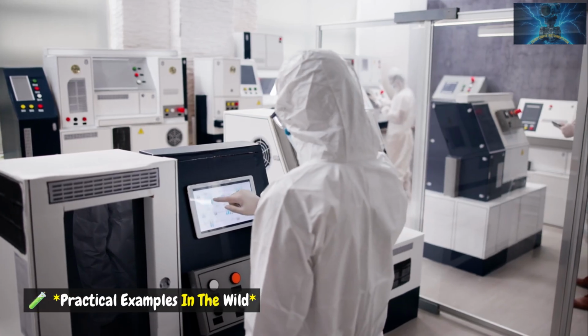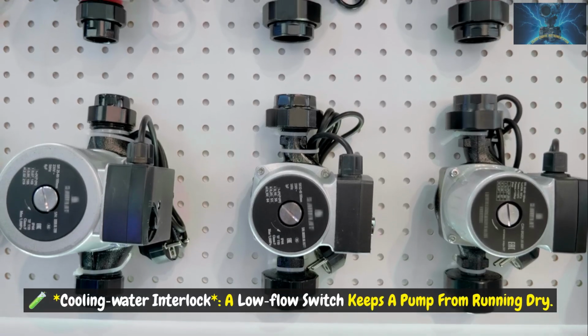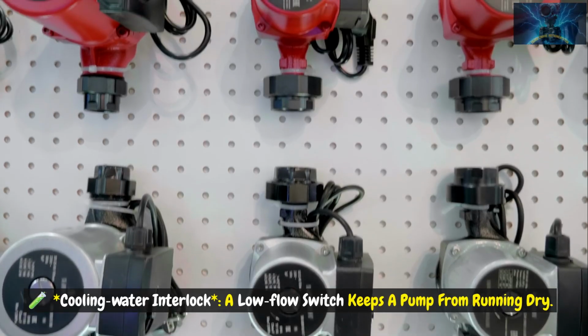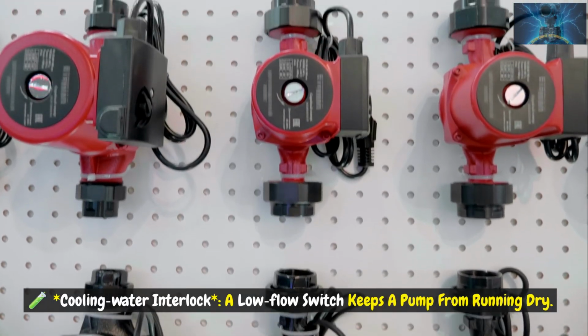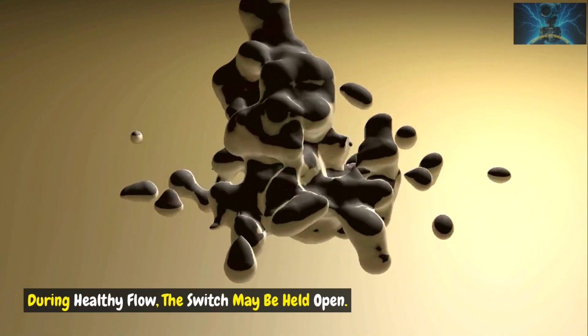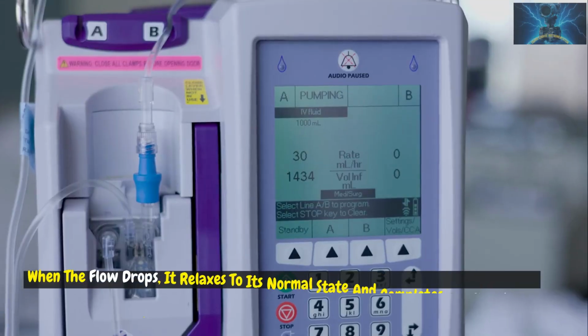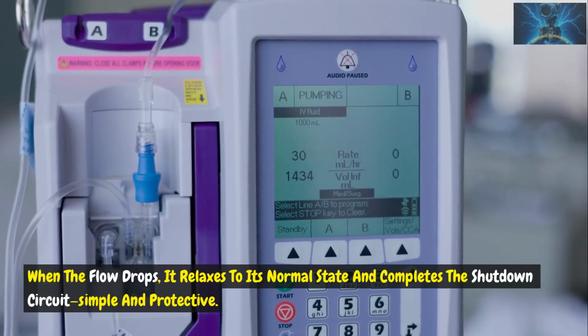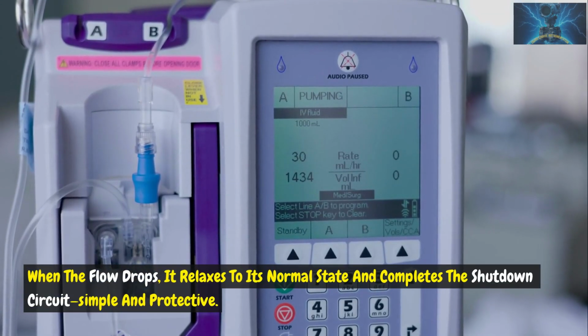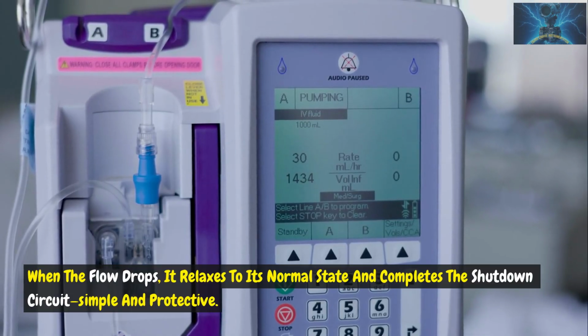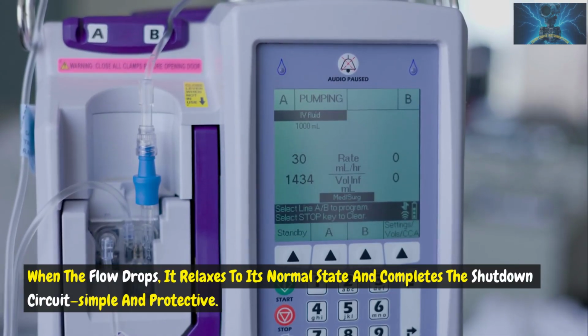Practical examples in the wild. Cooling water interlock. A low-flow switch keeps a pump from running dry. During healthy flow, the switch may be held open. When the flow drops, it relaxes to its normal state and completes the shutdown circuit, simple and protective.